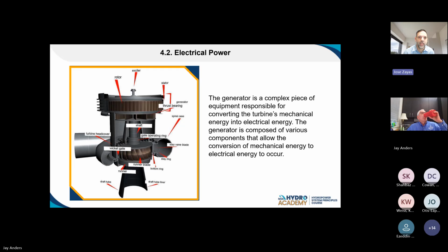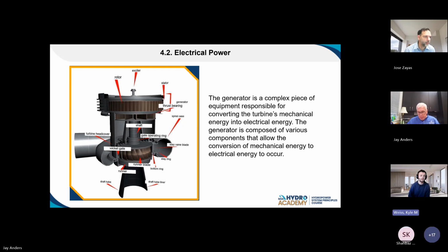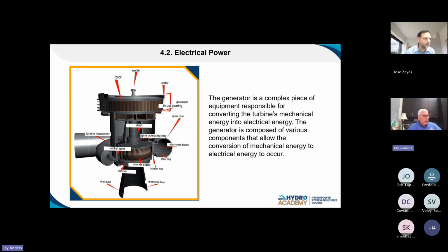We have another question, hands up from Kyle. Yeah, hey, could you talk about hydraulic short circuiting and ternary units as it refers to the diagram that you have up? Thank you. Yeah, great question. Where we're seeing ternary units nowadays, and just so everybody understands, where I have seen them, they may be in other areas, but we're looking at ternary units typically in the newer pumped storage plant designs. Really, we're looking at a way to have super fast control. You would have a short circuit, as Kyle shared, a flow path that would basically come out of the discharge of a unit and allow it to go back into the suction of that same unit.